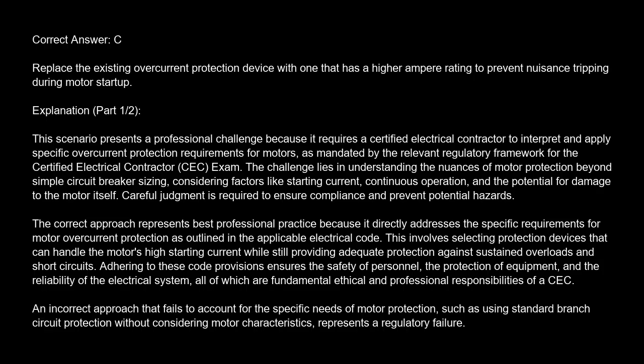The correct approach represents best professional practice because it directly addresses the specific requirements for motor overcurrent protection as outlined in the applicable electrical code. This involves selecting protection devices that can handle the motor's high starting current, while still providing adequate protection against sustained overloads and short circuits. Adhering to these code provisions ensures the safety of personnel, the protection of equipment, and the reliability of the electrical system, all of which are fundamental ethical and professional responsibilities of a CEC.